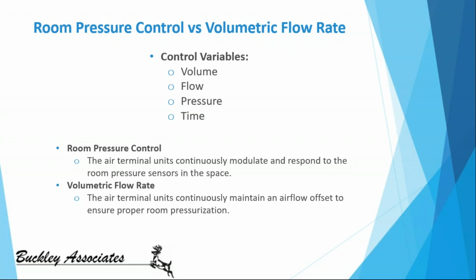So how we control our air control devices, and what type of air control devices we're going to have, is the first question we need to ask. And the preferred method of control in these isolation rooms is always going to be volumetric flow rate. It simplifies everything, and it takes some of the variables out of play. As I said earlier, that doesn't mean that pressure sensors are not going to be required. That just means we're going to use them to verify that the system is functioning properly, to maintain safe working conditions for the patient, the nurses, and the doctors, so everybody in the facility.